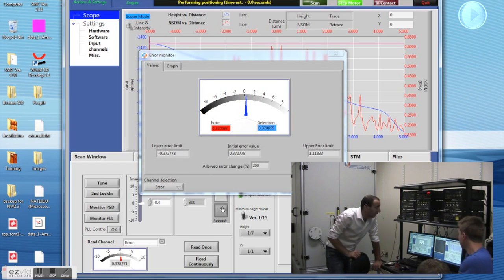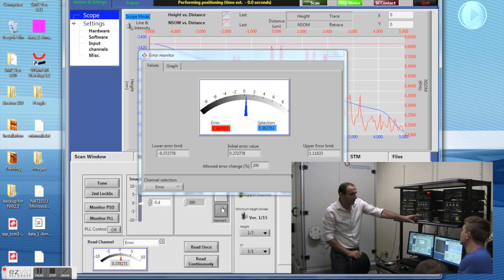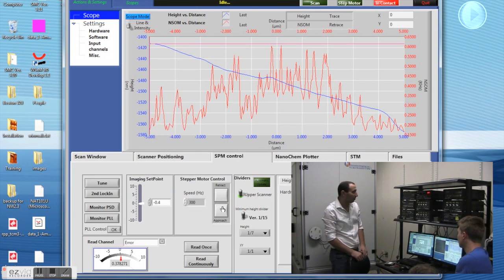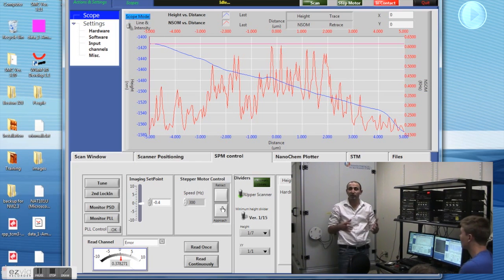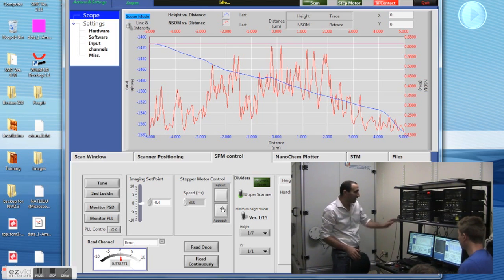So the tip is coming down, and all the signals and the voltages that we are applying in X, Y, and Z can be easily monitored here, and they are accessible, similar to the lock-in amplifier signal. So in case you want to synchronize or to work with these signals externally, you can easily get them from the outside. We will shortly explain also about that. So is the tip in feedback? Yes, it tells me it's in feedback. Also the software tells it's in feedback.